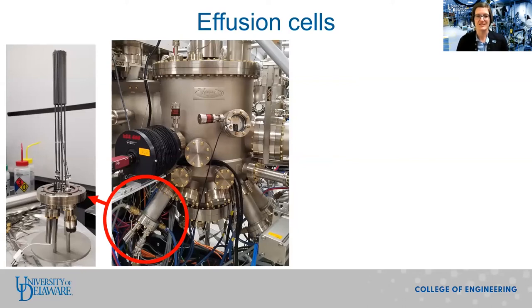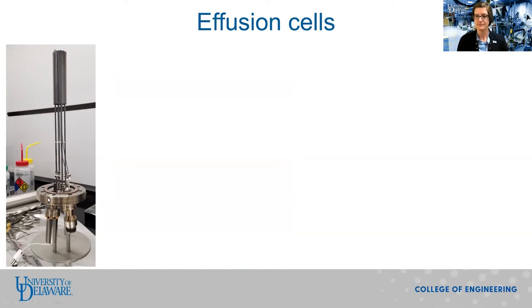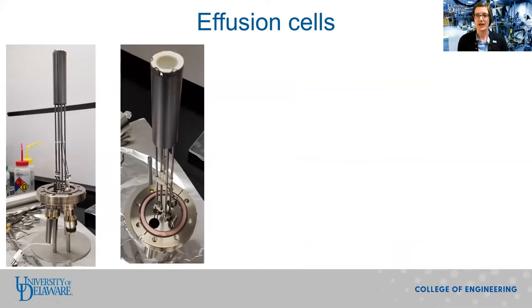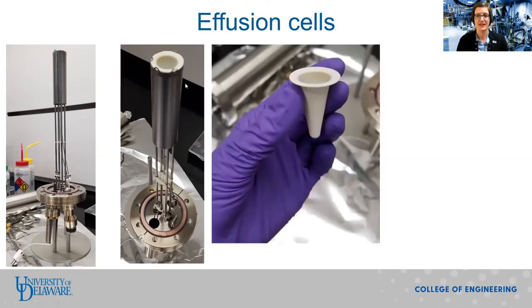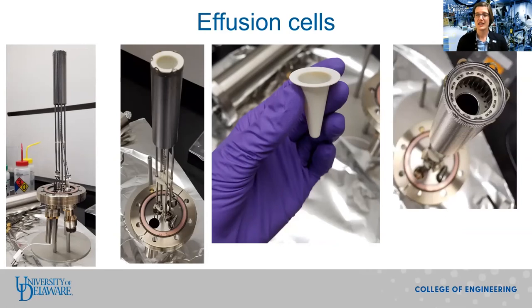Here are some photographs of the effusion cells. The effusion cells attach to the growth chamber, as shown in the red circle. Each MBE can house up to 10 effusion cells, enabling in principle the growth of a film with 10 different elements in it. In this photograph you can see three effusion cells, as well as two blank spots. When we pull the effusion cell out of the MBE, you can see the power couplings and the temperature readouts. In a top-down view, you can see the white ring — that's the crucible that holds the source material. Here's a picture of the crucible when it's pulled out of the effusion cell. If we pull the crucible out of the effusion cell, you can see the heater filament, which heats up the crucible to allow the material to evaporate.